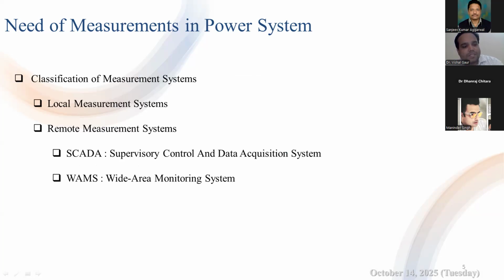So measurement systems in microgrids and power grids fall broadly into two categories. One is the local measurement system. The second one is the remote measurement system. In a local measurement system, values are available at the local end only, at substations only. They are not communicated to remote locations. Whereas in a remote measuring system, the values are sent to the control center, which may often be hundreds of kilometers away.